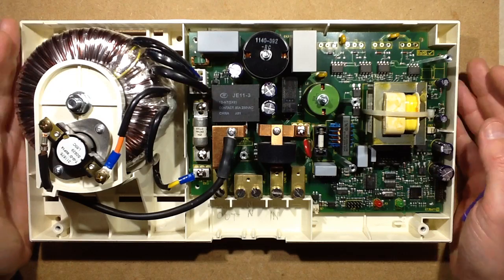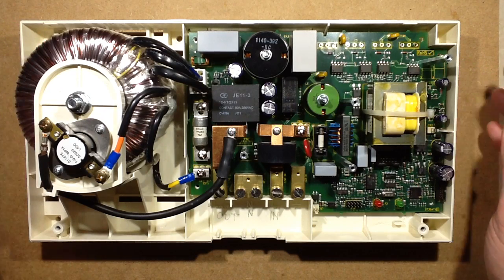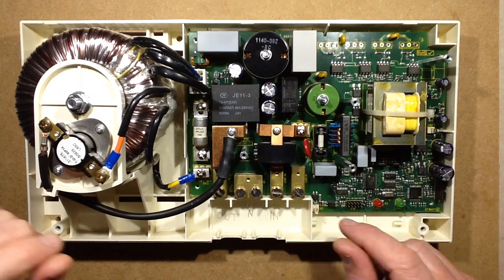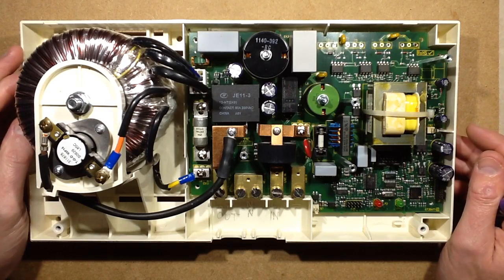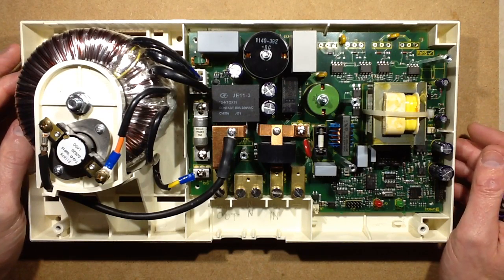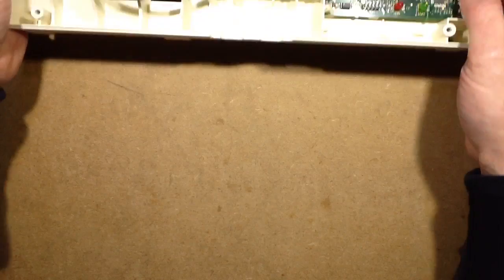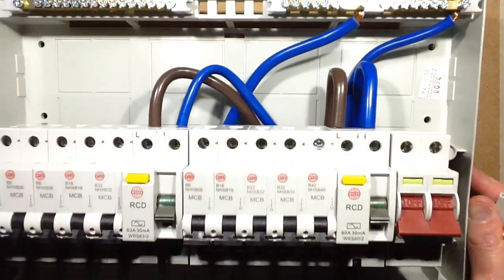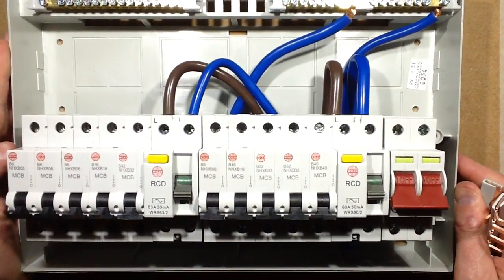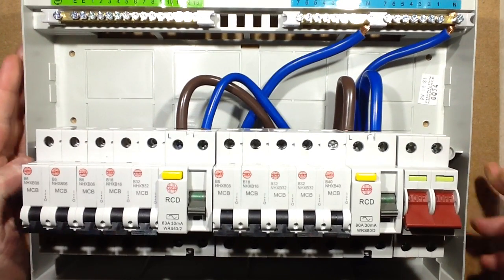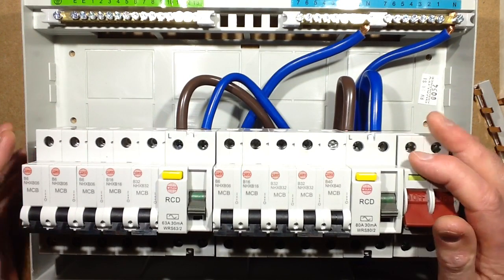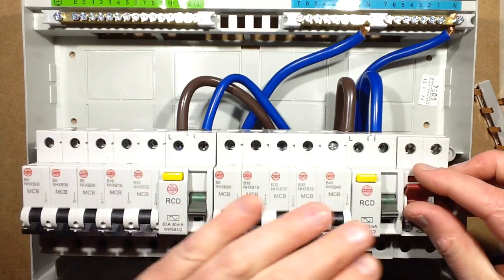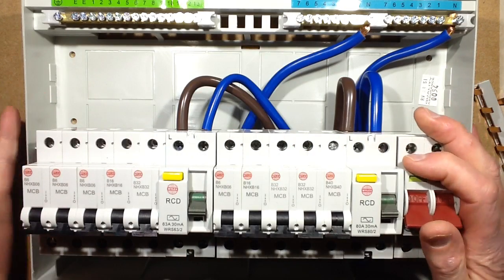They present it as a simple task, that they can get their guy to come out, just stick it into your consumer unit, and that'll be it. It requires a significant modification to your consumer unit. I'll show you a consumer unit. In fact, consumer unit is the name for a home distribution board in the UK. So here is a typical split load consumer unit, made of plastic for maximum combustibility. It's got the main incoming breaker, which is not a breaker, it's just an isolator.